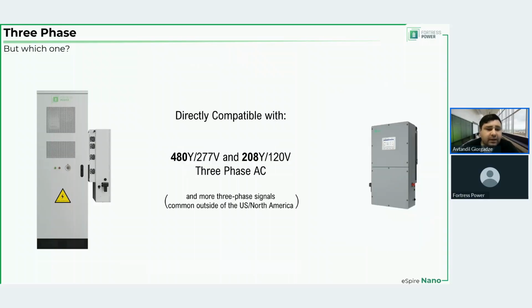It works with 480 volt and 208 volt AC supplies. It provides that type of output. It works with AC PV in that configuration, and it works with the generators that deliver this signal. Although we focus on 480 volts and 208 volts here in the US, it also can work with other AC signal types. It's just we're not going to cover those during this webinar because our understanding is that the attendees are, if not the majority of them from the US, then at least from North America.